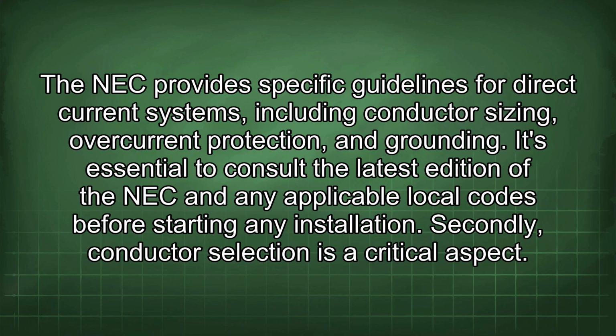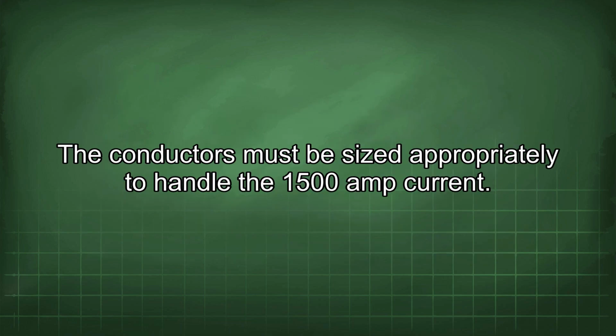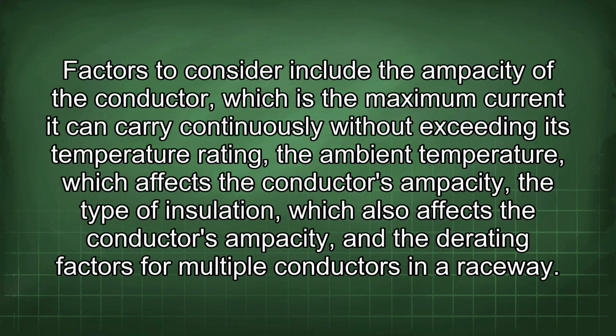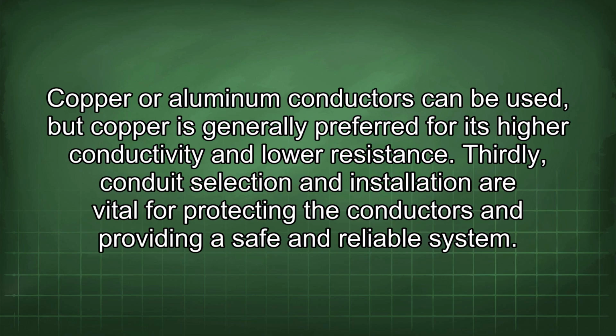Secondly, conductor selection is a critical aspect. The conductors must be sized appropriately to handle the 1500 amp current. Factors to consider include the ampacity of the conductor, which is the maximum current it can carry continuously without exceeding its temperature rating, the ambient temperature, which affects the conductor's ampacity, the type of insulation, which also affects the conductor's ampacity, and the derating factors for multiple conductors in a raceway. Copper or aluminum conductors can be used, but copper is generally preferred for its higher conductivity and lower resistance.